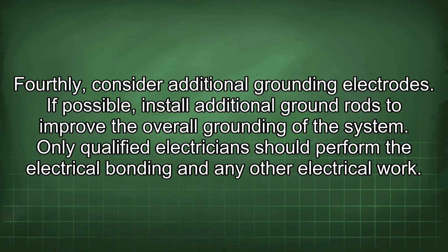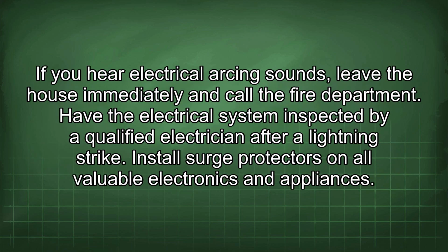Fourthly, consider additional grounding electrodes. If possible, install additional ground rods to improve the overall grounding of the system. Only qualified electricians should perform the electrical bonding and any other electrical work. If you hear electrical arcing sounds, leave the house immediately and call the fire department. Have the electrical system inspected by a qualified electrician after a lightning strike.